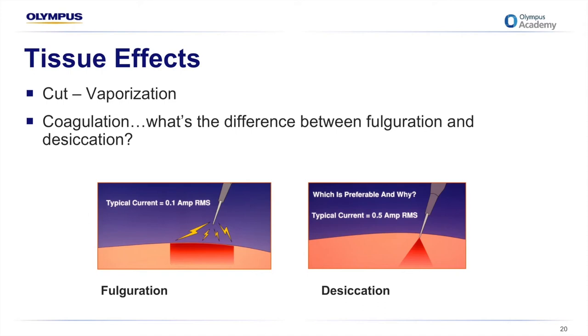Desiccation is a low-powered coagulation and can be accomplished with monopolar, conventional and advanced bipolar applications. Tissue dehydrates as a result of direct contact with the electrode.